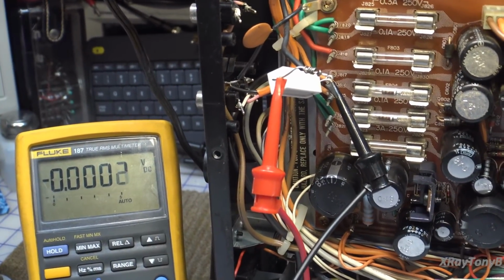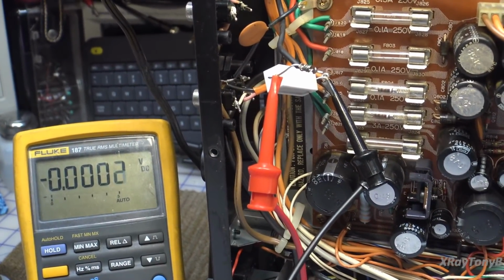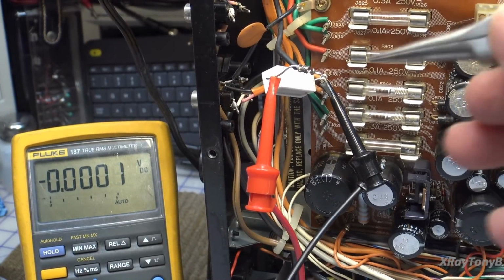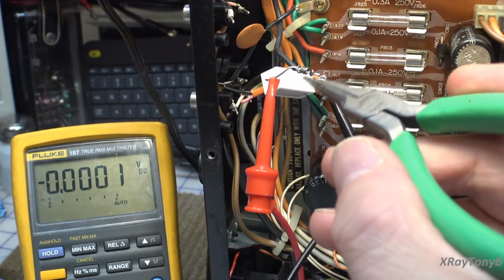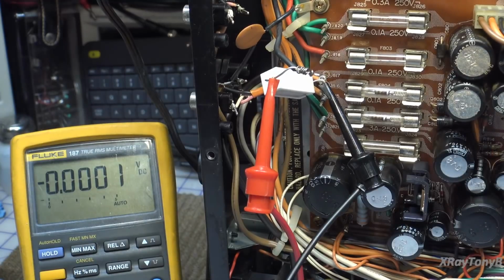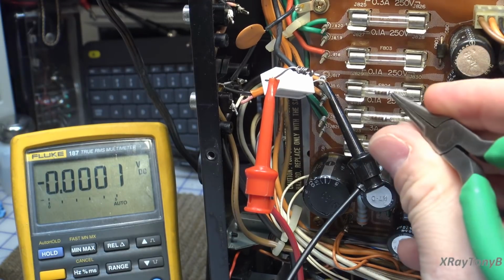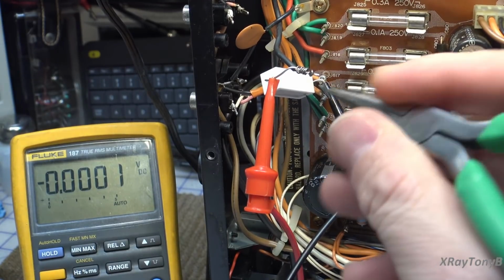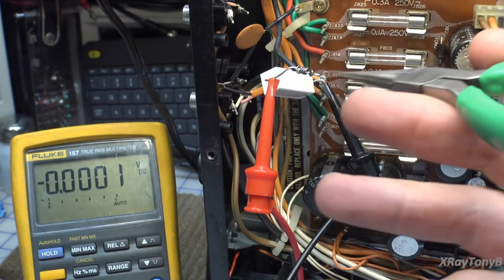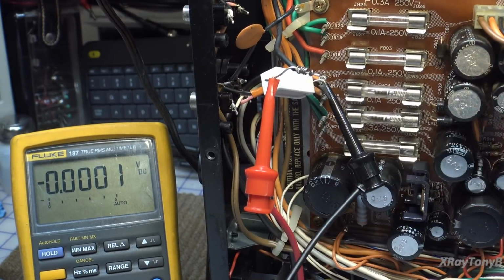Now why 2.7K? That resistor will limit the current - it won't let the current get above roughly 100 milliamps or less, so we won't damage our transformer or any components. It also means we won't exceed the limit of the fuses and blow them. All that'll happen is the voltage drop across it will increase with current.